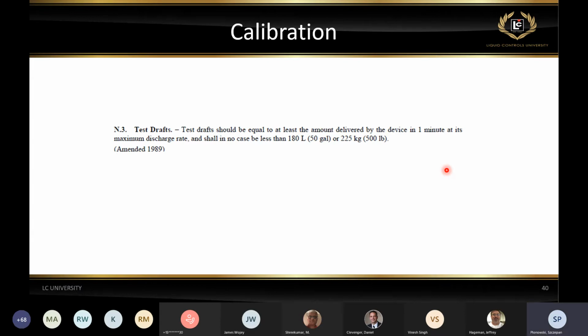This is really a point from what's called Handbook 44. That's one of the guidelines here in the United States defining a calibration. And generally, that test draft, or the size of a prover, should be at least a volume that can be delivered through the meter that's being tested in 1 minute. So if you have a meter that is rated for 100 gallons a minute, if you pump a product through it for 1 minute, you're delivering 100 gallons, and that is the size of a prover.